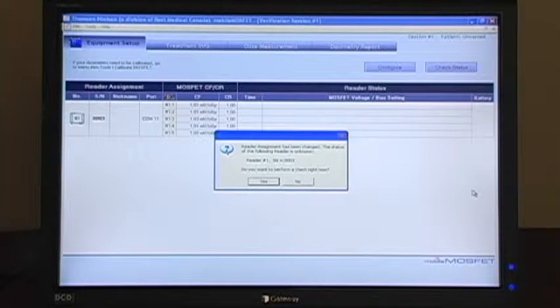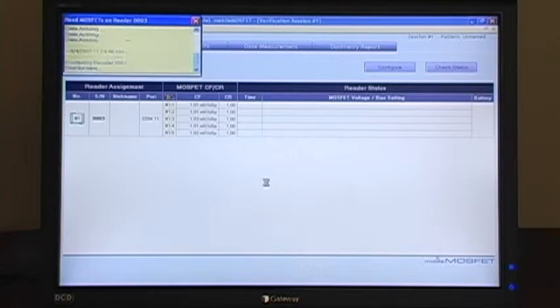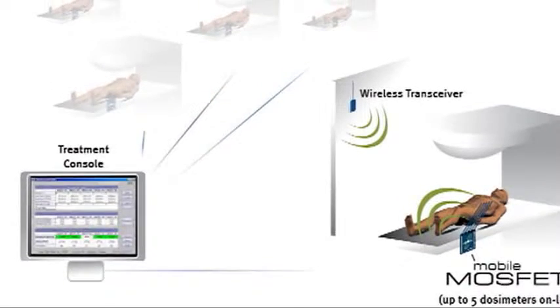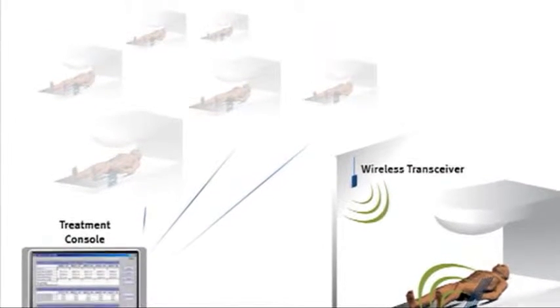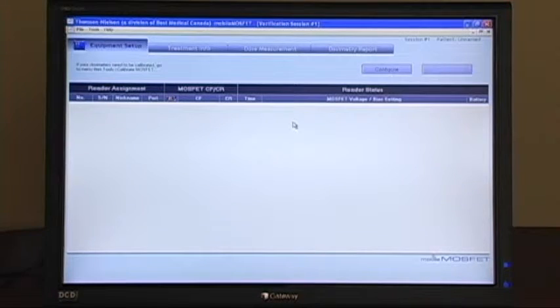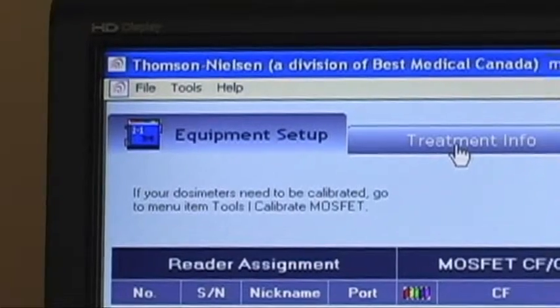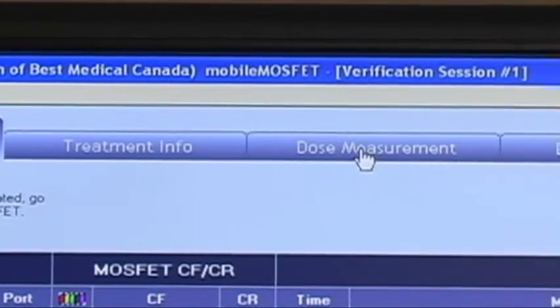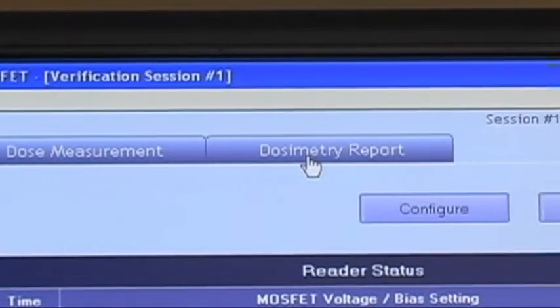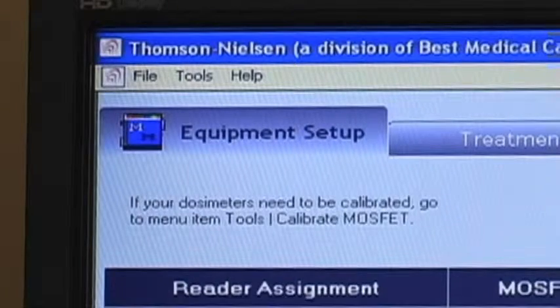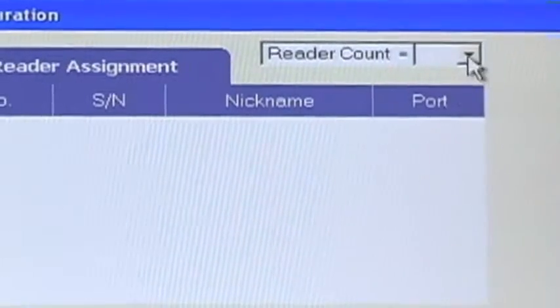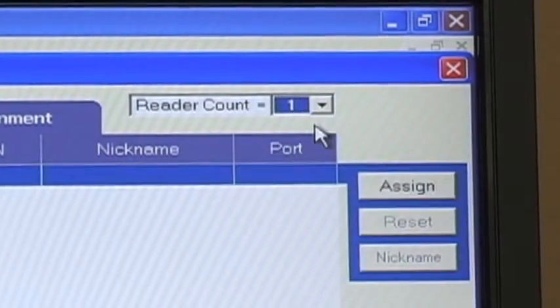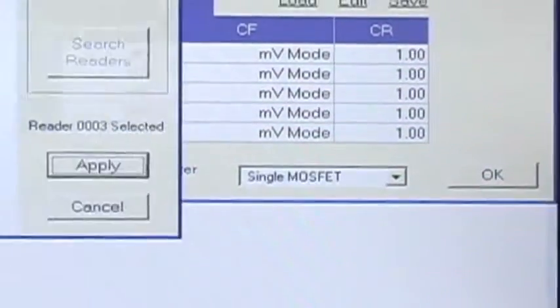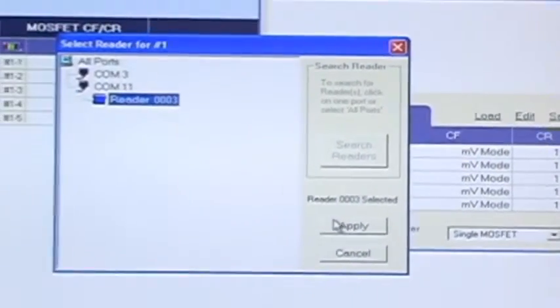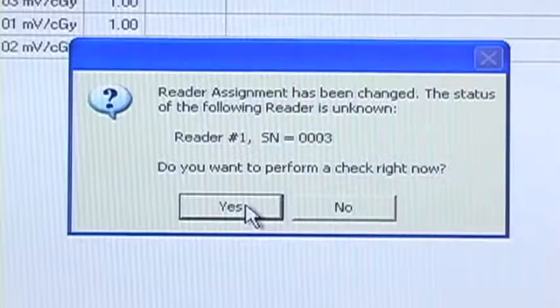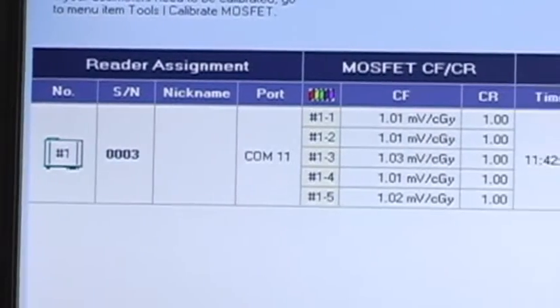The Mobile MOSFET is completely software-driven, which enables it to be controlled outside of the room, making it easy to collect both dose data and calibration data. There are 4 main tabs on the initial screen, one each for equipment setup, treatment information, dose measurement, and the dosimetry report. The Equipment Setup tab is used to initiate the connection between the hardware and software. Once established, information is provided on the hardware status, including the amount of charge remaining in the battery, how much dose has been accumulated on the dosimeters, and what the calibration factors are.